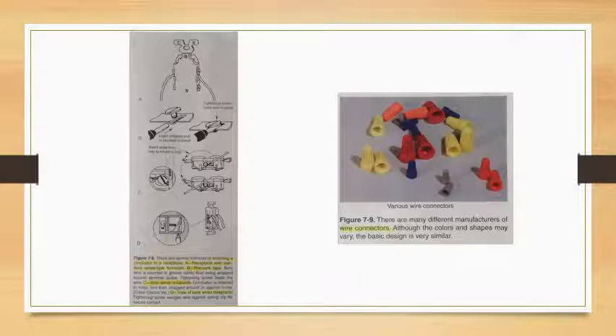Attaching conductors to device terminals. Solid conductors are connected to screw type terminals. The ends must be formed in a loop for a proper connection. Use a needle nose pliers or similar tool to form a curved hook on the conductor as shown in figure 7-6. This must be connected clockwise onto the terminal. When the screw is tightened, the open end of the loop will be pulled inward, making the connection more secure. If the screw turns against the open end of the formed loop, this will result in a poor connection that may be unsafe.